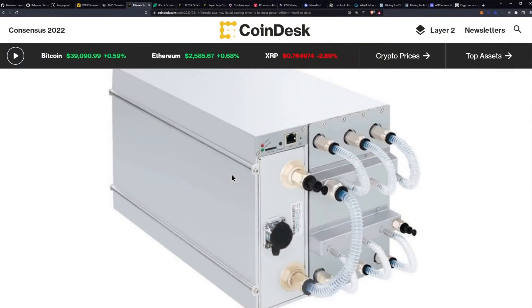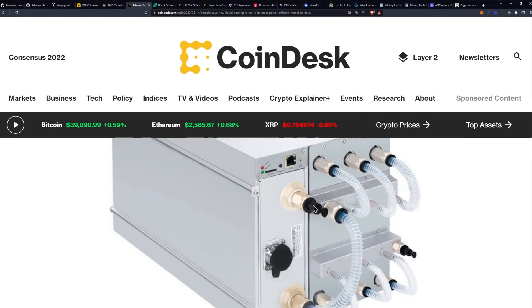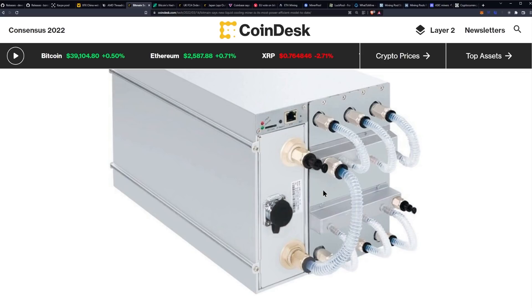Maintenance on the liquid cooling one is going to be interesting. I really don't like the tubing they used here — that's worrisome. You're going to have all of these connections. When purchasing these hydro mining rigs, the worrisome part about these all-in-one units, as opposed to a submerged tank, is that with a submerged tank you're going to have one pump basically powering a whole bin of miners, which reduces the amount of failure points. Here, instead of just a couple fans on an air-cooled unit and the power supply, now you have every single one of these fittings and tubes to worry about as well.